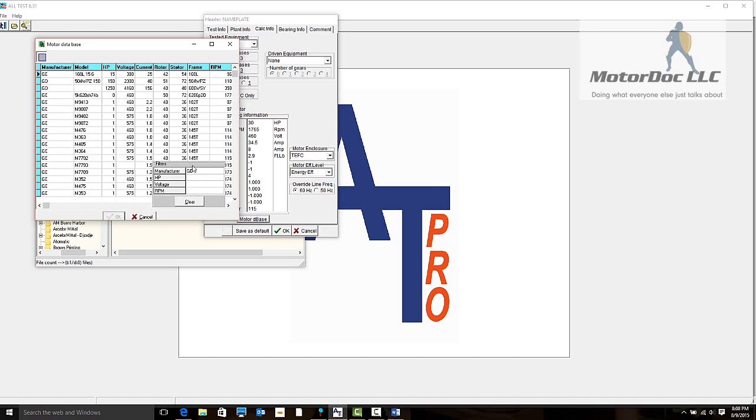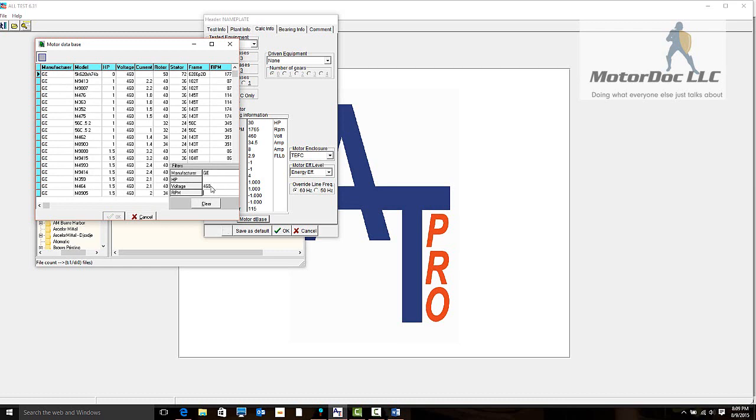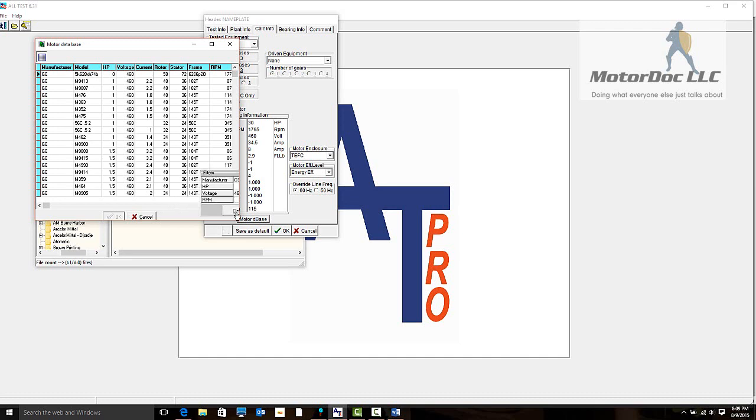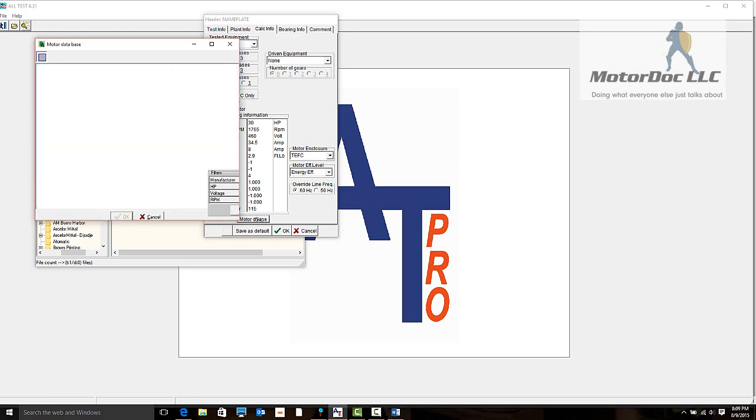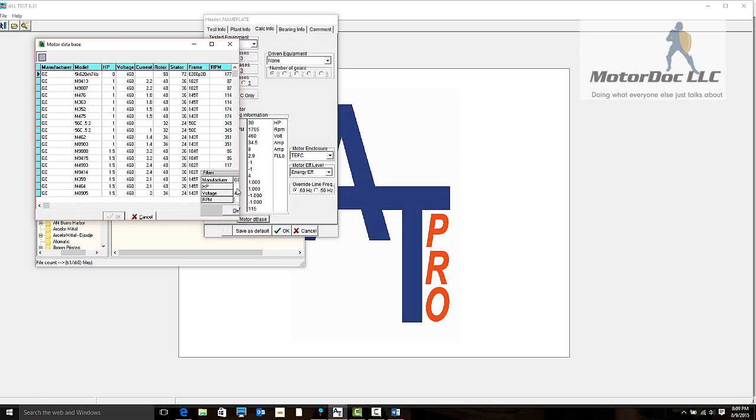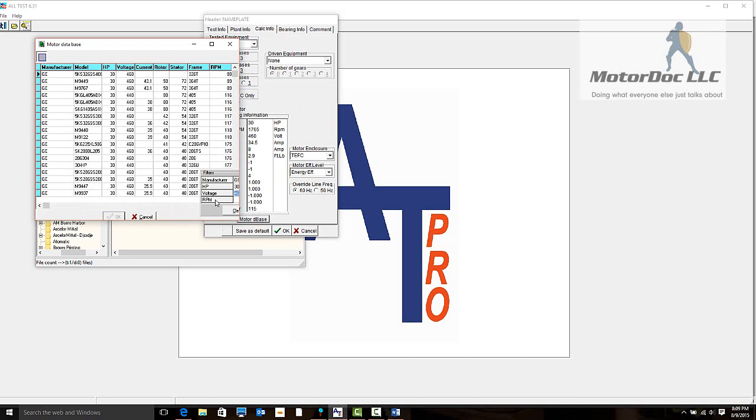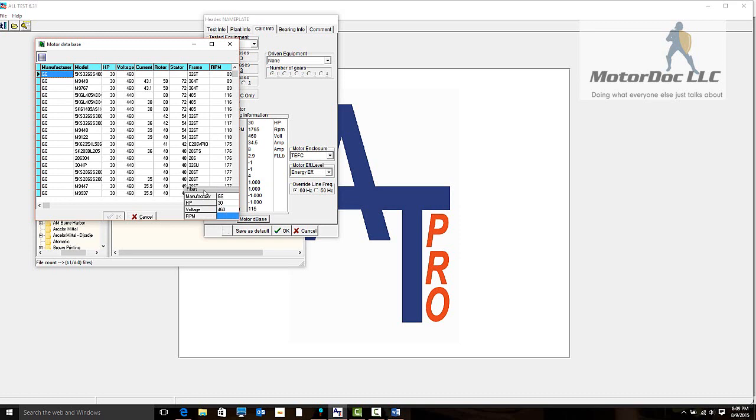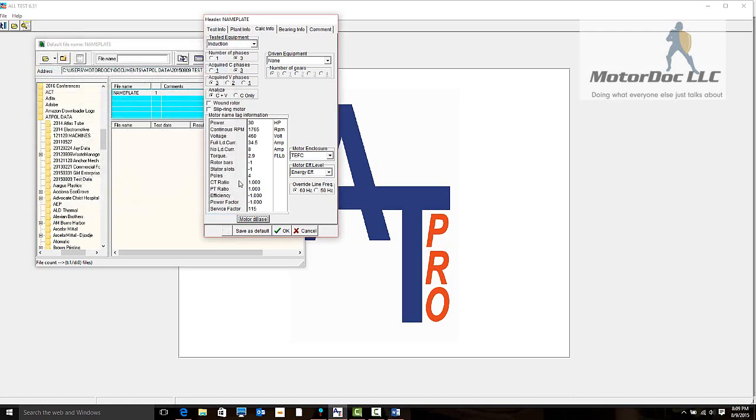In here I can look for, this is a GE motor. We hit enter, and now you can see we have all of this information here. Let's add in 460 volts and enter again. Let's go ahead and enter in as well the horsepower, which is 30. We've got 30 horsepower motors. This is a 286T frame. If we scroll down to 286T frame, we will find a number of machines. The main thing I notice is all of these have 40 and 48. So we're going to say that this is 40 and 48.